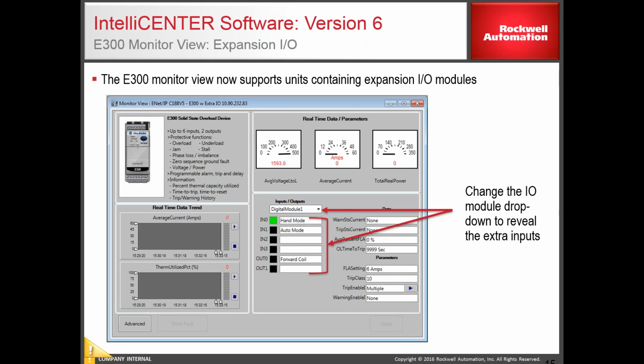Well, let me ask you this: is this with just the software, or is this with a retrofit for the IntelliCENTER Motor Control Center itself? Because if you have the Ethernet switches in the MCC and you don't have the IntelliCENTER software, you can go back at a later date and upgrade with the software. You can get the data disks created. You can install the software so that you can go in and start monitoring the devices. As far as retrofitting the MCC with Ethernet when you don't have any of the switches, I'm not sure about that. It's an engineering project, and it can be done, but it's an engineering project. You have to specify all the devices that you're going to put in, and it can be done. Typically, it's a new project, or it's an add-on to the existing IntelliCENTER.